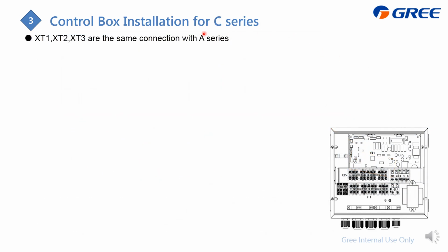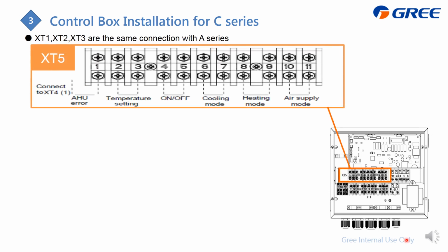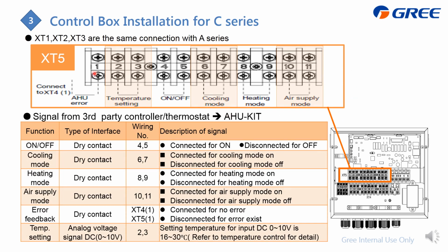Next is for the C series, and the XT1, 2, 3 is the same as the A series, so we can skip. And the difference is the XT5 and XT4. First is for the XT5, as it can support the third-party controller, and here is just for that. And you will find that this one is actually the dry contact signal, and we support on-off, the cooling mode, heating mode, and also the air supply mode, and this is the error feedback. We also support the temperature setting by the analog voltage signal. It is DC. And then later I will show you the detail.